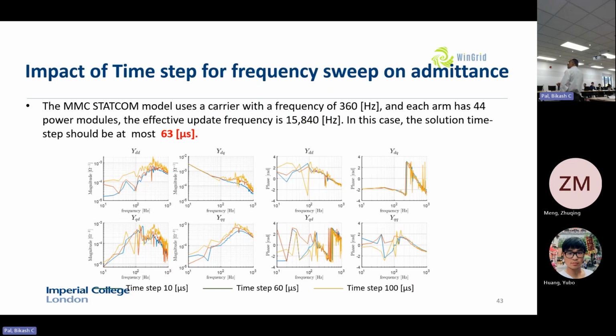So then we do the impact of the time sweep. We have the whole EMT model, and the converter, the STATCOM, is producing the voltage. On top of that, we add one voltage source of variable frequency, and whatever current we get from that, we sample. On that sample we apply the impedance estimation algorithms.